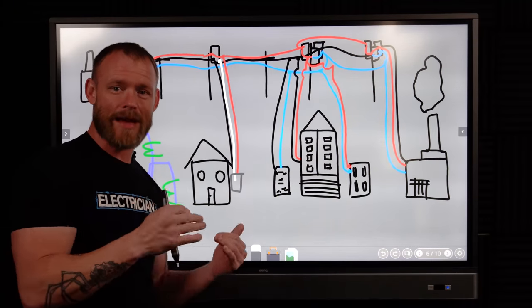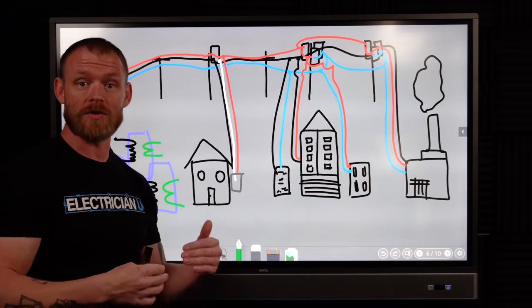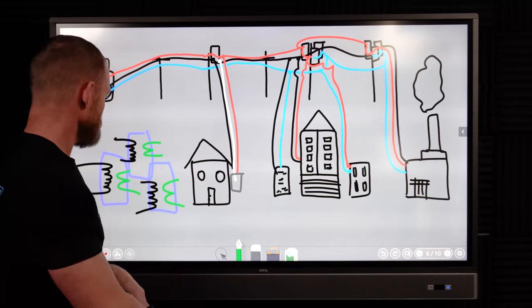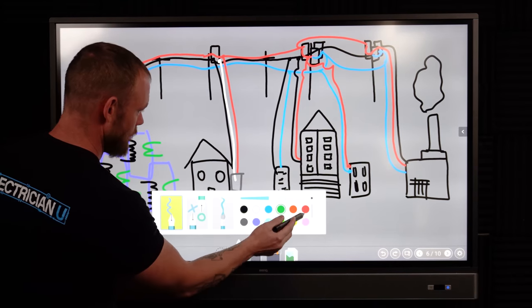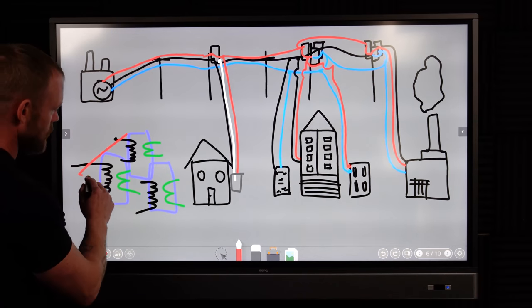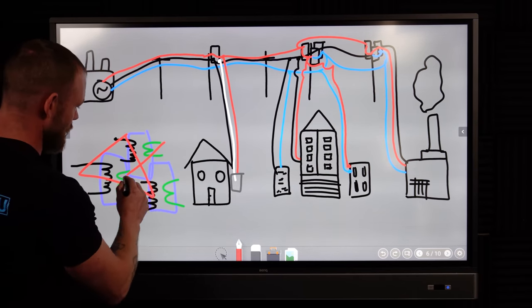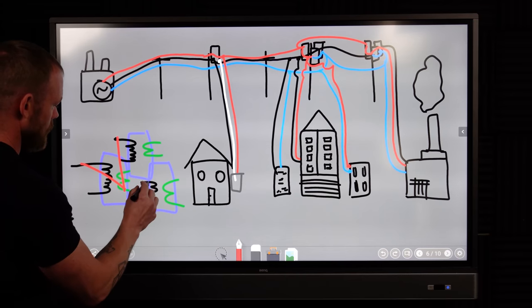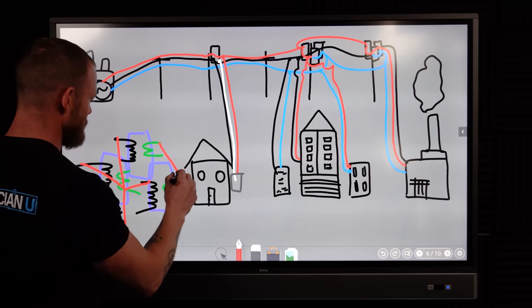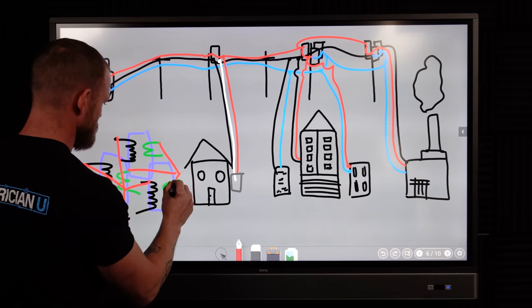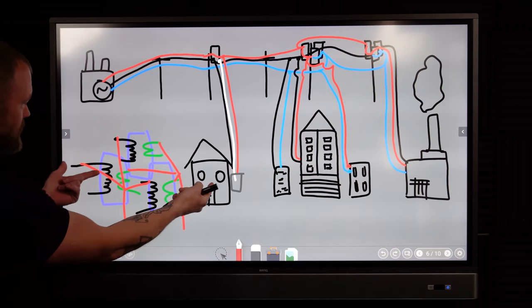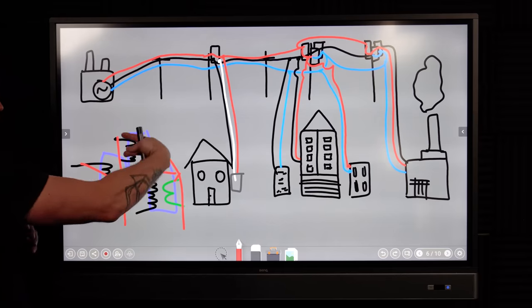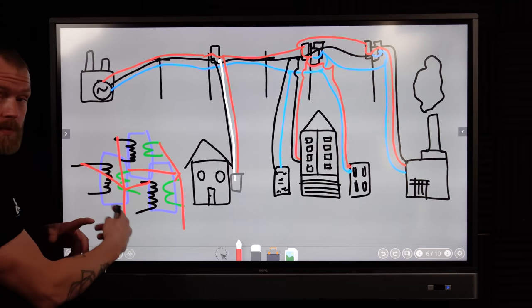The secondaries can get wired together in different ways. You can have what's called a wye configuration — written as 'Y' — or a delta configuration which is a triangle. You wire the transformers together in either a triangle on the primary and secondary sides, or in a Y configuration. In a wye, there's a neutral point where all of them come together — that's where we tap the neutral. Three phase means three loops or circuits; single phase means a single loop.